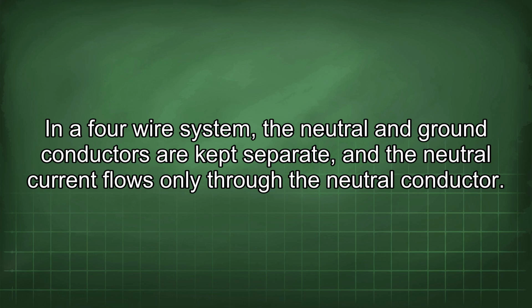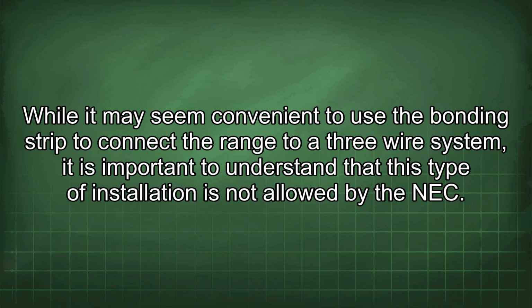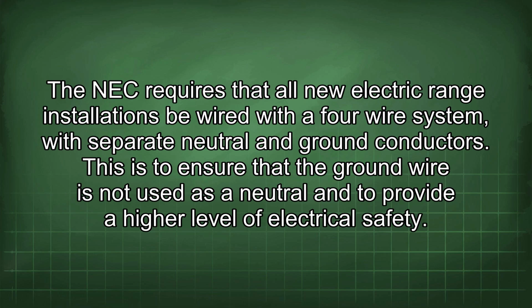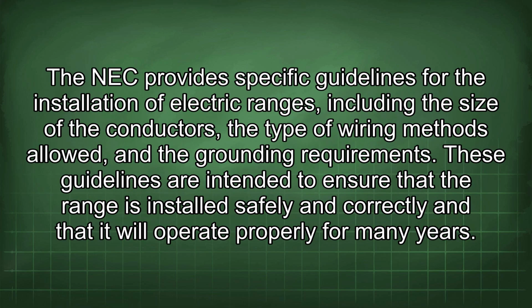While it may seem convenient to use the bonding strip to connect the range to a 3-wire system, it is important to understand that this type of installation is not allowed by the NEC. The NEC requires that all new electric range installations be wired with a 4-wire system with separate neutral and ground conductors. This is to ensure that the ground wire is not used as a neutral and to provide a higher level of electrical safety. The NEC provides specific guidelines for the installation of electric ranges, including the size of the conductors, the type of wiring methods allowed, and the grounding requirements.